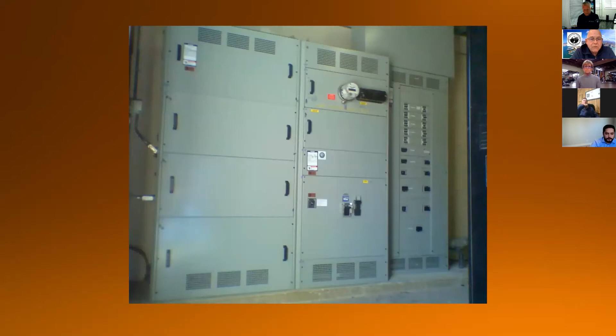Here's an example of installing a transformer high on a wall to free up floor space. A lot of commercial buildings we work on are served with 480 volt power, good for HVAC equipment and lighting. We transform the 480 volt to 120 volt to be used for lower voltage equipment and receptacle power.